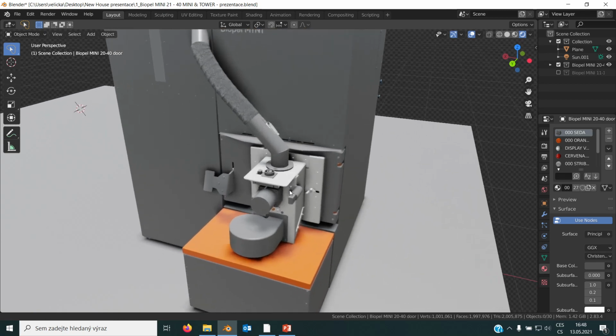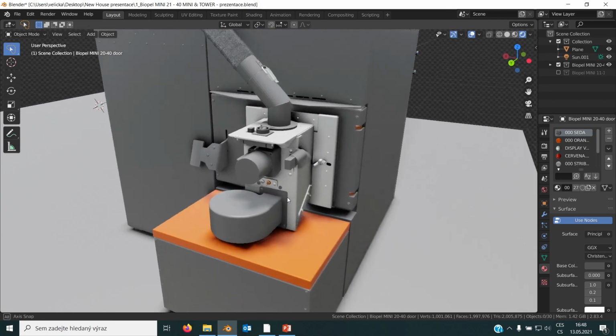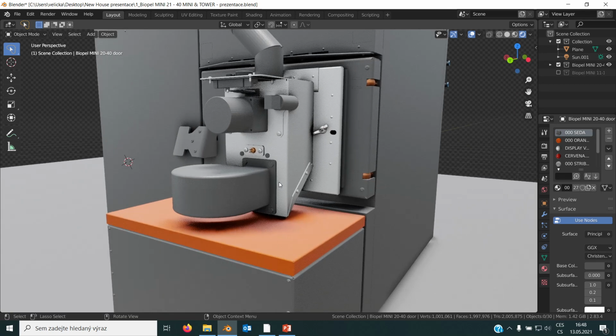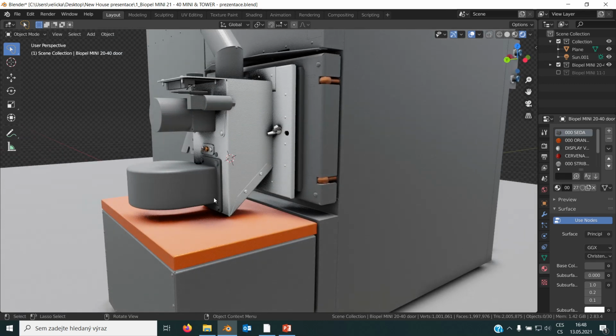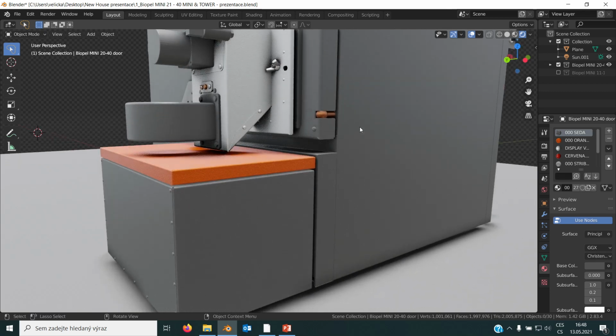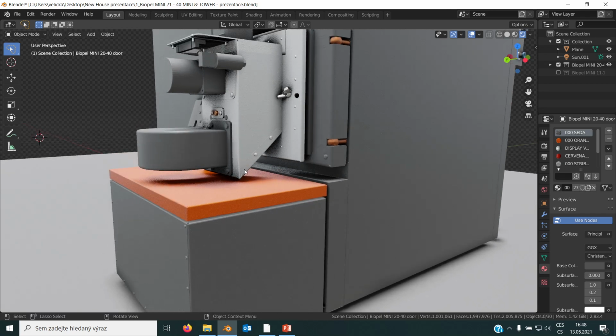Speaking of the burner itself, there is one change on the burner, and this is the position of the fan. Before, with V9 Premium, we had the fan from below, from the bottom of the burner, but because the Biopel mini boiler is small, and as you can see below we have the ash container here, we had to move the fan position to the back side of the burner.